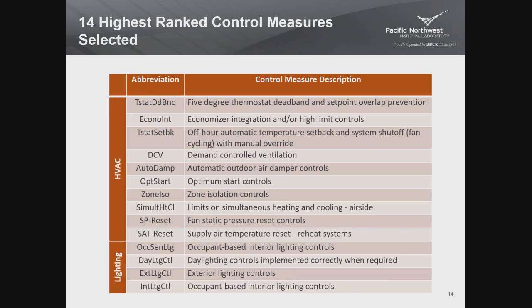Exterior lighting controls, this is mostly about requirements that say you have to turn the exterior lighting off when it's light outside. So parking lot lighting and building facade lighting and walkway lighting needs to turn off if it's light enough. And then the last one, occupant-based interior lighting controls. It sounds a little like the occupancy sensor, but it is a different requirement. Occupancy sensors are only required in some spaces, but almost all buildings require what we sometimes refer to as sweep control. That is a lighting system that turns all the lights off in a building by schedule. So that's the last of the 14 requirements.